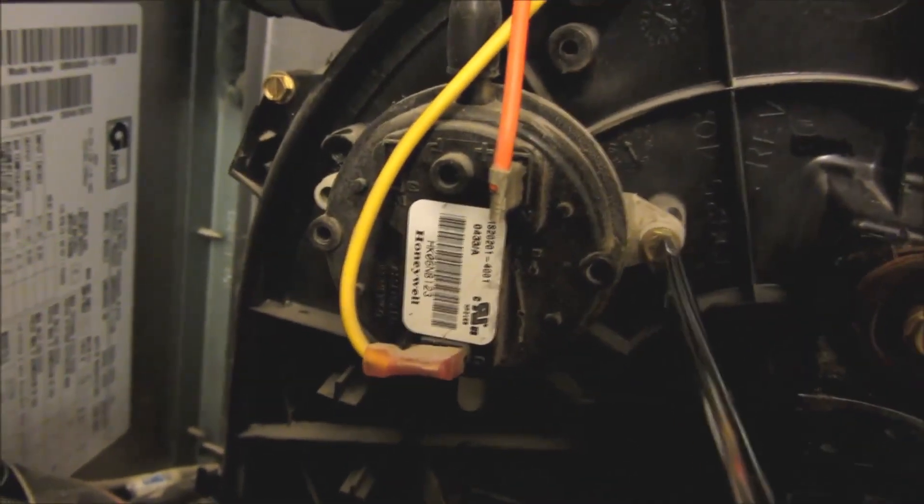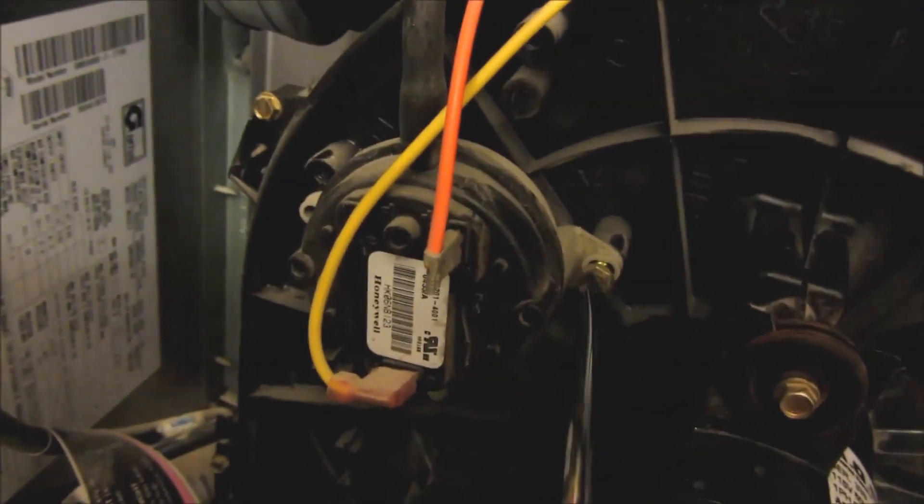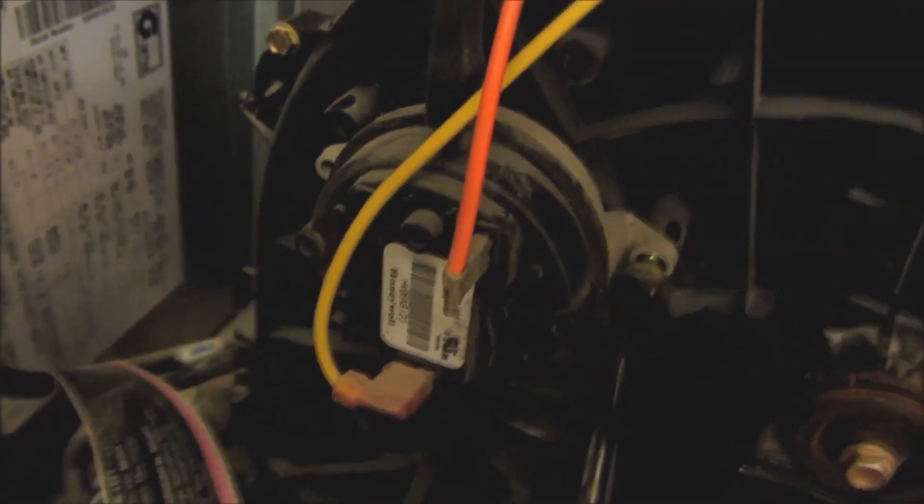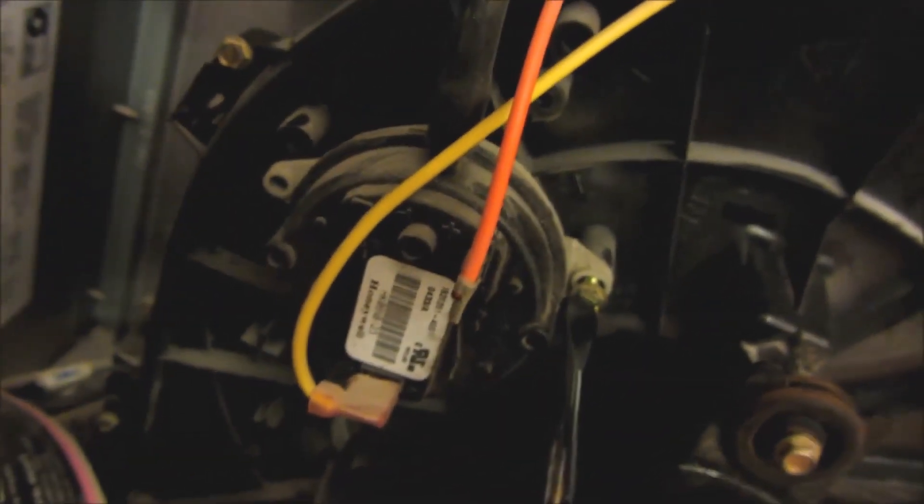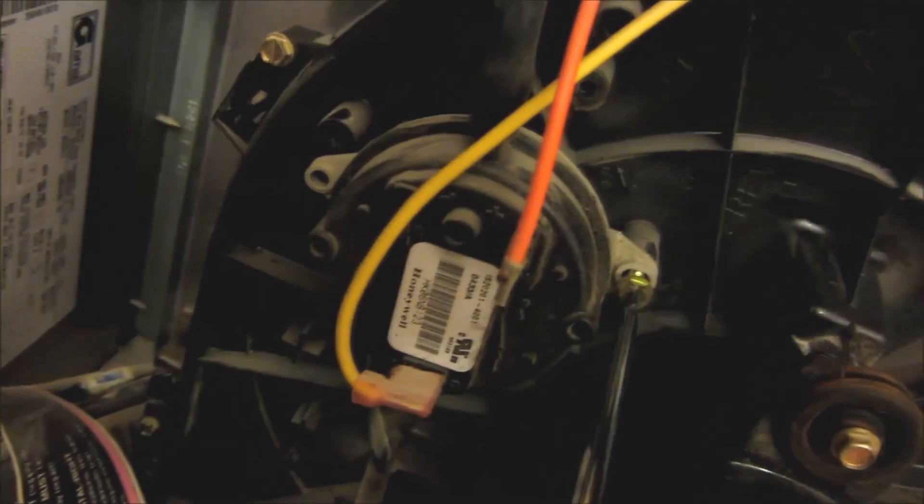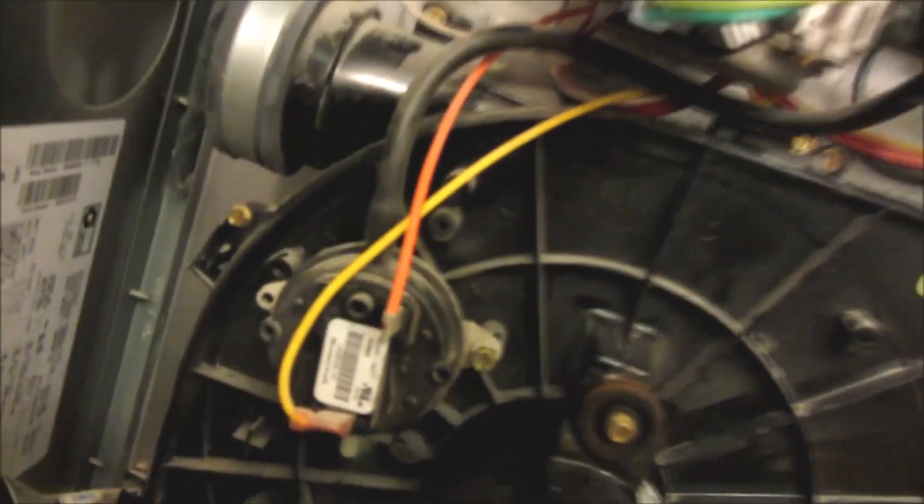The next thing is just to take off the pressure sensor. The pressure sensor is mounted by the two screws. So remove the two screws. They're pretty deep, they're about three quarters of an inch. You'll see at the bottom of the pressure sensor is a tube. I actually pulled out that tube, just wiggle it gently.